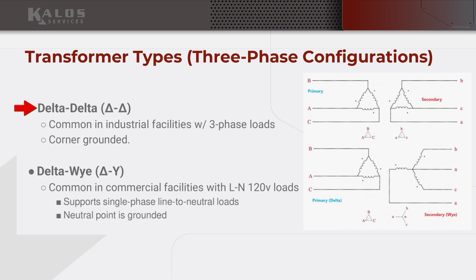Delta is used more in industrial settings where you don't have a lot of need for a line to neutral load. There's some benefit to delta systems in that if you lose B phase, since this is a closed triangular loop, your system can still function, albeit at a lower capacity.